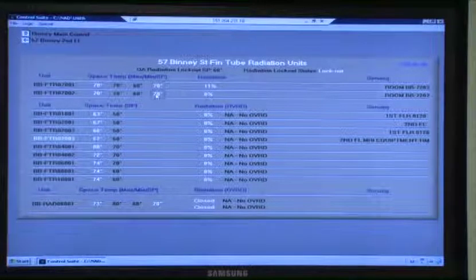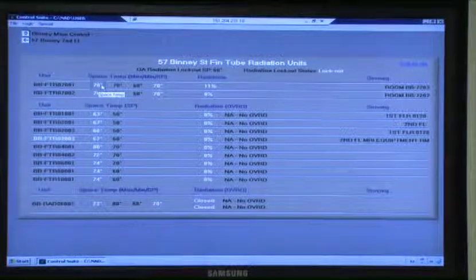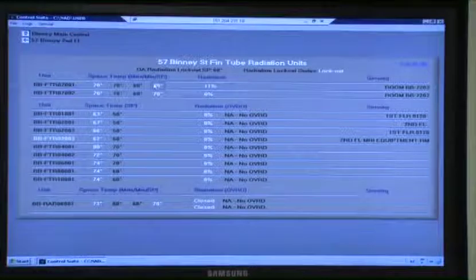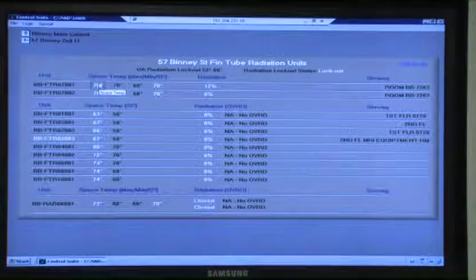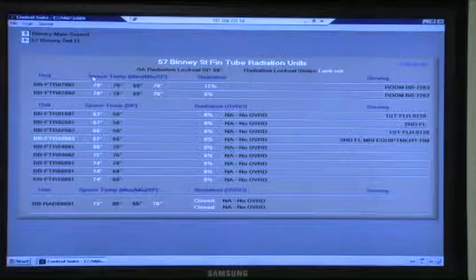When you get on the floor and you click on the T-stat, you get the same screens, just showing you what's on the sensor. That's your resultant set point on the temperature. Thermostat is 70 degrees, your actual space temp is 70. It's just dead nuts on. Great, perfect.